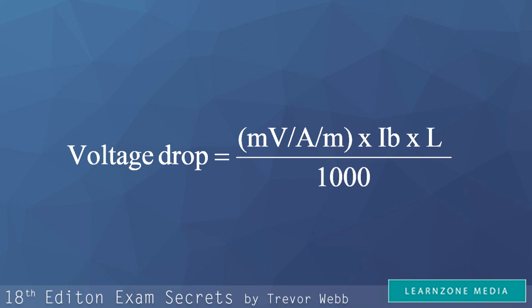The best place to make a note of the formula is at the top of page 383 next to regulation 6.4 voltage drop in consumers installations. Why here? Because, and I say this all the time to my students on the 18th edition course, you always start looking for any answer at the beginning of the book in the main table of contents.